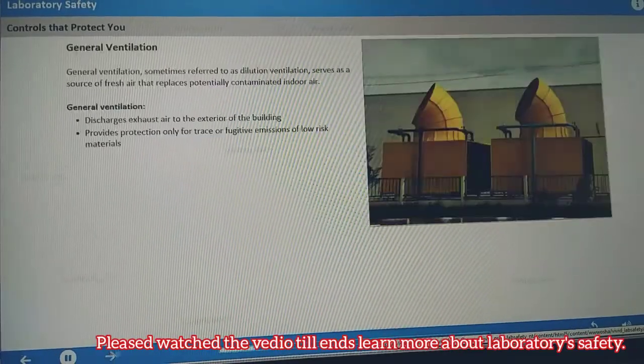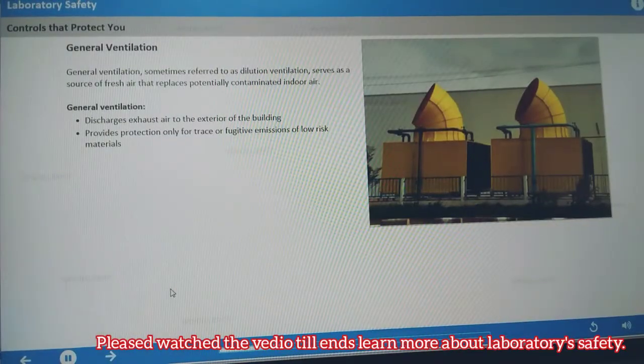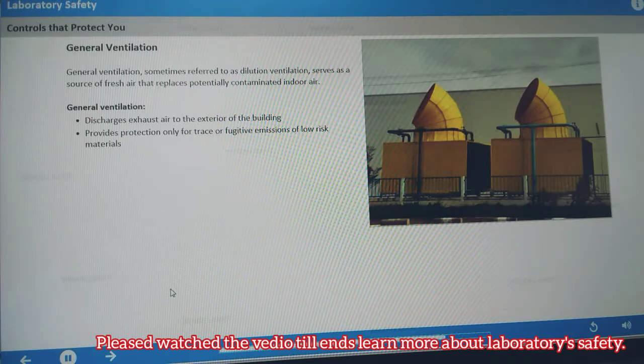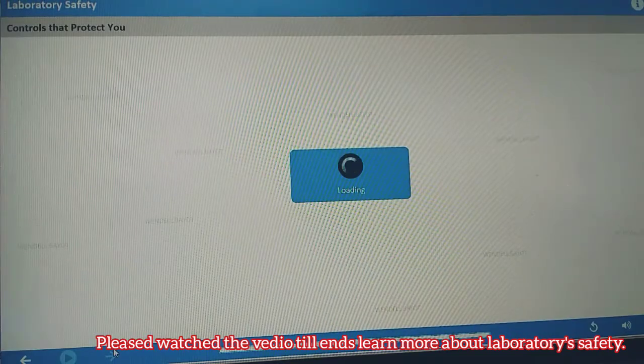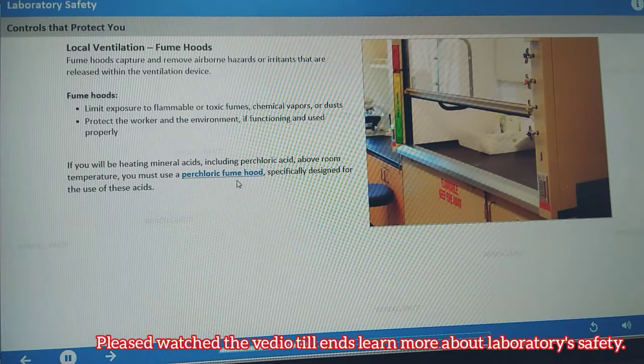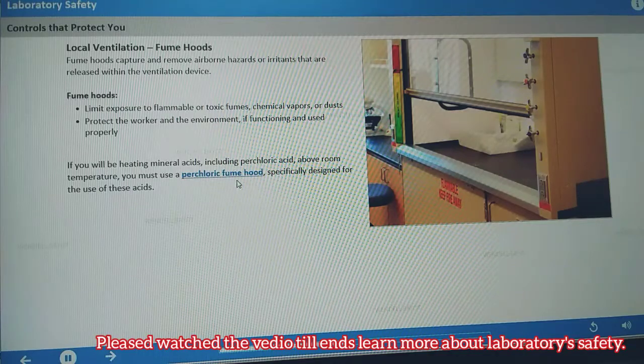Ventilation can be general or local. General ventilation serves as a source of fresh air that continuously replaces potentially contaminated indoor air. Although many laboratory buildings are designed to provide a high number of air changes per hour, general ventilation only provides protection for trace or fugitive emissions of low-risk materials. One of the most important safety devices in a laboratory is a properly functioning fume hood, which controls airborne hazards that are released within the ventilation device.